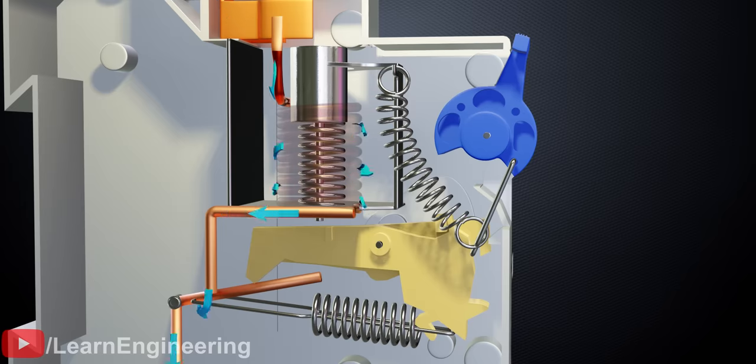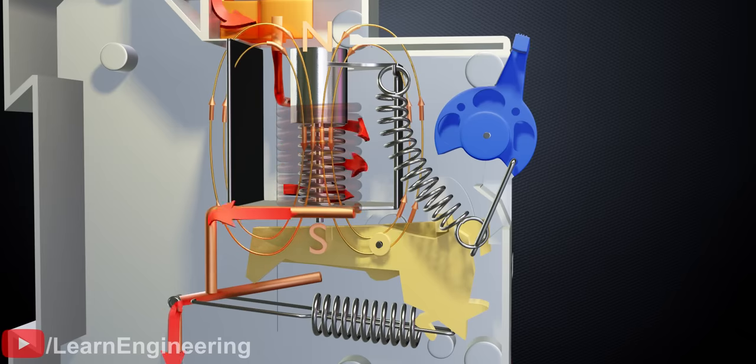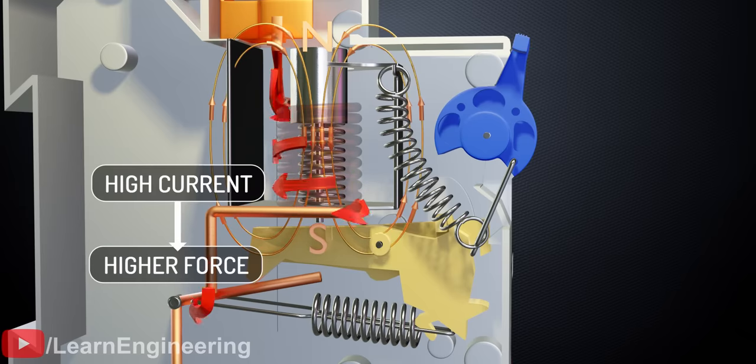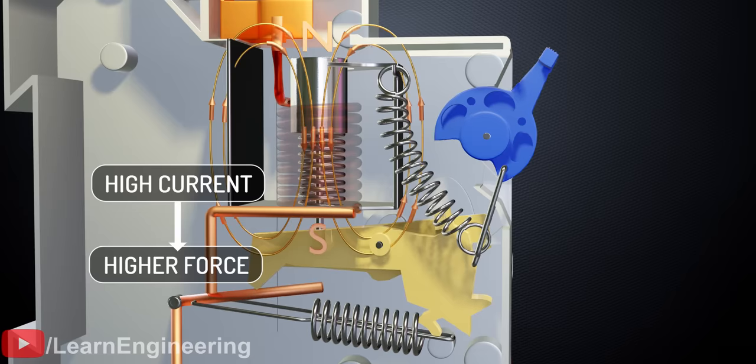You might be wondering, in normal current flow, why isn't this cylinder attracted down? Well, the force in normal current flow is not high enough to overcome spring tension. Whereas short circuit current can go up to 10 to 100 times the normal current, the force is quite high, so the circuit trips.